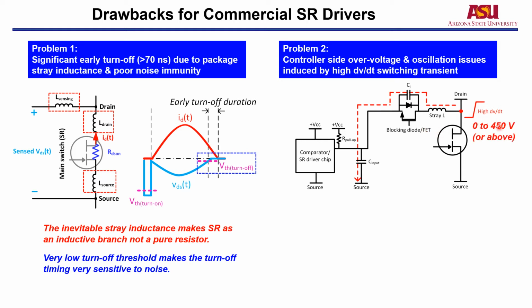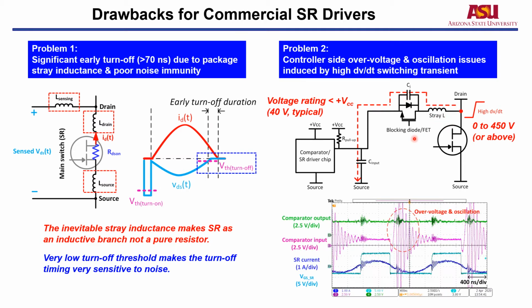During the high dV/dt transient, for example, the battery voltage is 450 volts or even above. This voltage is really high, and the junction capacitance of the blocking diode or blocking FET will be in series with the input capacitance of the comparator or the SR driver chip. Because the voltage rating for this chip is very low, typically below 40 volts, overvoltage may occur. Meanwhile, the network capacitance will oscillate with stray inductance. In that way, we may have overvoltage and oscillation issues for the comparator or SR driver chip input.